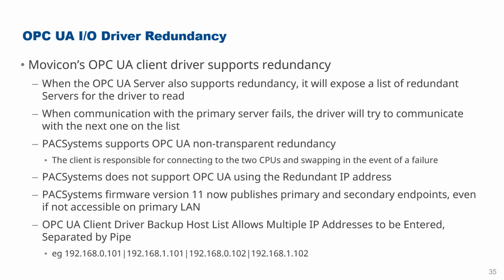The OPC-UA I/O driver is a special case. Movicon does support OPC-UA client driver redundancy, and the way this works is we're using a special aspect of driver redundancy, which is around transparency of redundancy. When the OPC-UA server supports redundancy, it exposes a list of redundant servers for the driver to read. The driver then automatically looks at communication with the primary server. If that fails, the driver will try to communicate with the next one on the list.